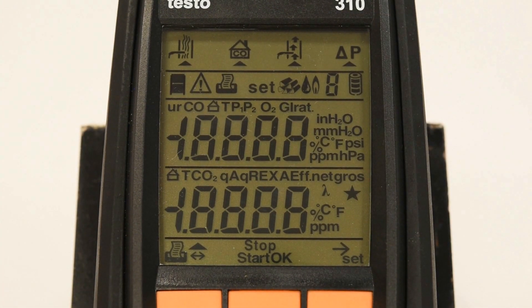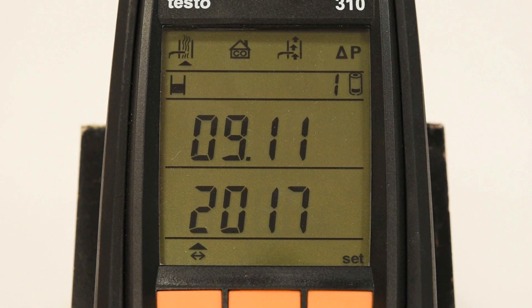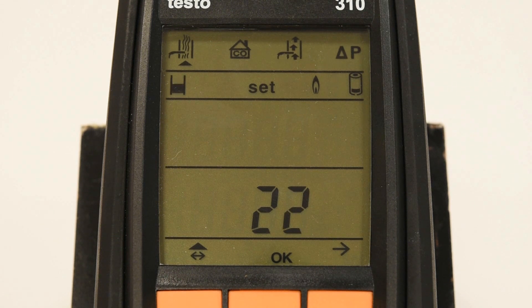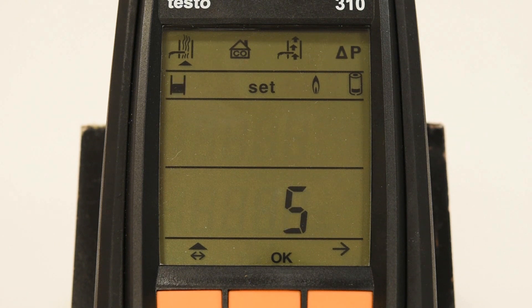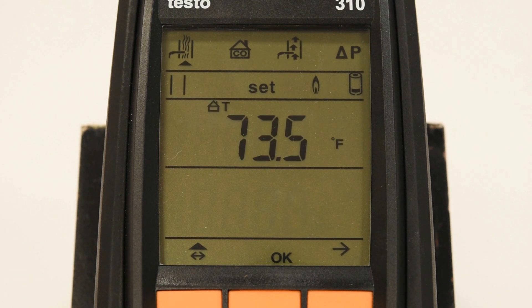When first turning on your Testo 310 combustion analyzer, you will hear your pump activate and will notice a 30-second countdown displayed on the screen. This is the sensor zeroing feature and will happen every time the instrument is turned on. It is important that whenever this zeroing function is performed, it is done in fresh air, preferably outside, so that a proper zeroing calibration is achieved.